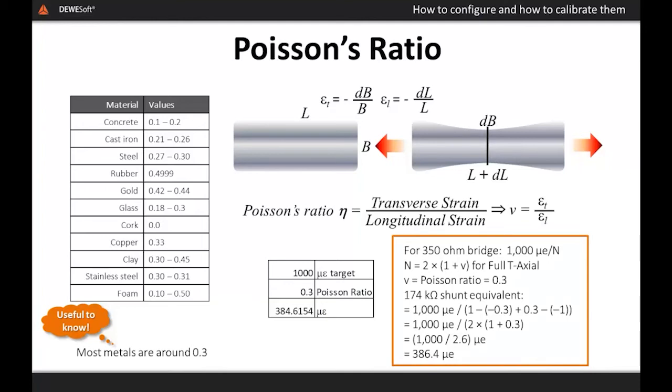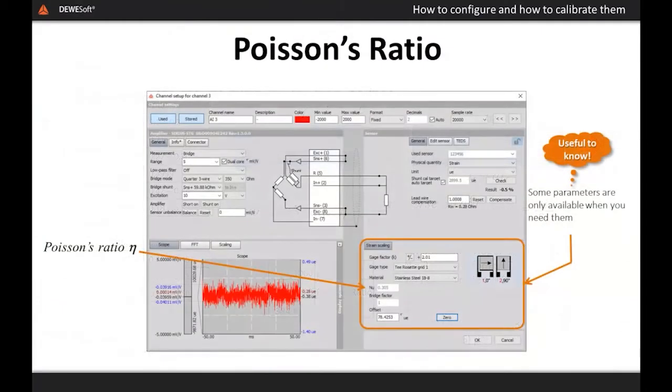Ironically, a lot of folks use 0.3 as a reference, and it does cover a large number of metals. But as you can see in this chart, this number can change quite dramatically, even on what appears to be similar materials. For later reference, you may want to make a note of the value for concrete in the upper left. Again, if the system that you are using is advanced enough, it will have an option to add these values or even simply select a material from a list.